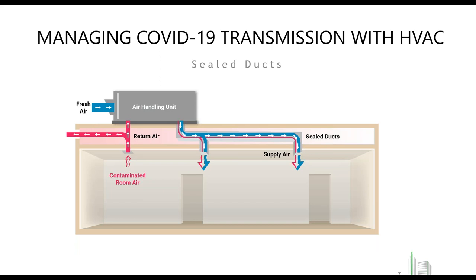So let's talk about why it's important to have sealed ductwork when we're trying to improve our ventilation and increase all of this, and then also how that helps save on energy as well. So this is an air handling unit system, and the blue is the fresh air coming in, and the red is the recirculated air. What's important in this diagram is that when the ducts are all sealed up, you bring in a lot of fresh air, which is what the guidance is right now, and that fresh air is actually making it into the space. So all the fresh air going into the air handling system and getting combined with the recirculated air is making it into the room.